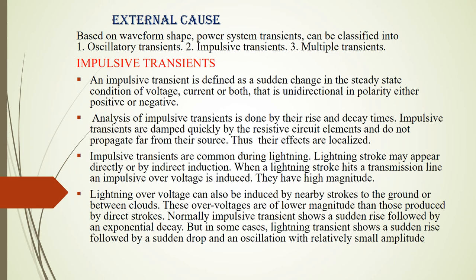Now coming to external causes. Based on the wave shape, power transients are classified into three types: oscillatory transients, impulsive transients, and multiple transients. The best example of an impulsive transient is lightning. During a direct stroke, when lightning strikes directly on a transmission line, an impulsive transient is created — it starts at a very high voltage and reduces to a lower value.